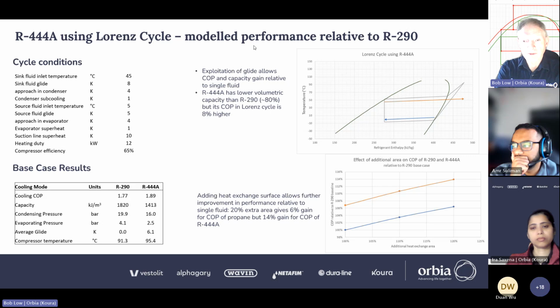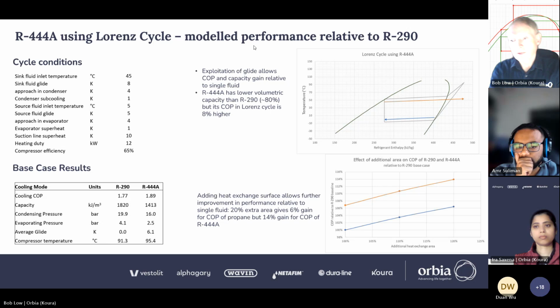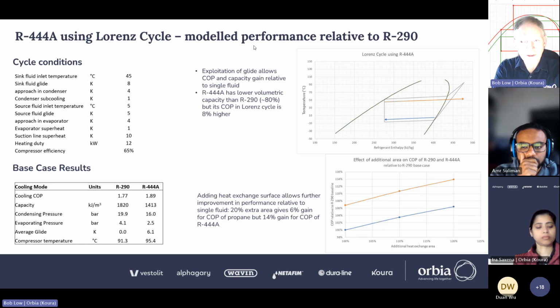Then the question is, can you gain more by adding more area to the heat exchangers? The answer is yes, of course you can. Eventually you get to the point where you've spent more on the heat exchangers than anything else, and it makes no sense. But if you start at 100% area and then add area, what happens? Well, with propane, if you add 20% more area, you get 6% more COP. If you add 20% more area to the blend, you end up with 14% more COP compared to the base case propane. And although it's maybe not too obvious from that 3-point graph, the gap between the two fluids opens up. So if you went to 30% area, you would get more benefit for the blend than you would for propane.